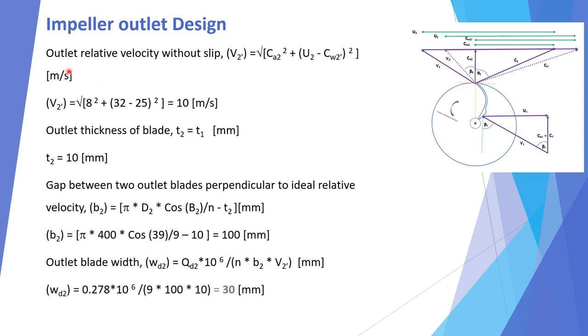Outlet relative velocity without slip: V2' = √(Ca2² + (U2 − Cw2')²) = 10 m/s. Outlet blade thickness T2 = T1 = 10 mm. Gap between two outlet blades perpendicular to the ideal relative velocity: B2 = (π × D2 × cos β2 / N) − T2 = 100 mm. Outlet blade width: WD2 = Qd2 × 10⁶ / (N × B2 × V2') = 30 mm.